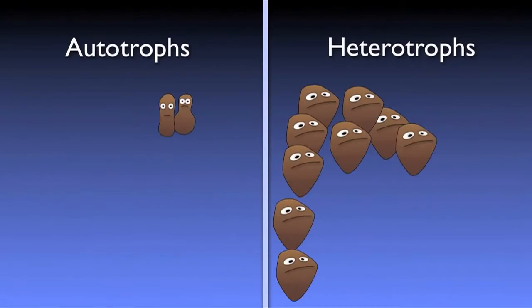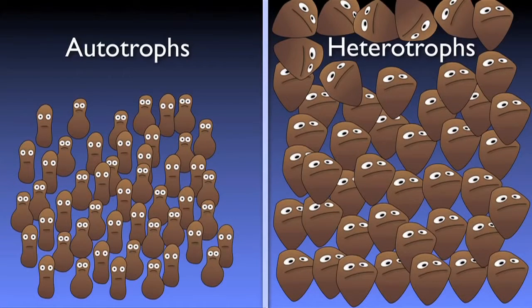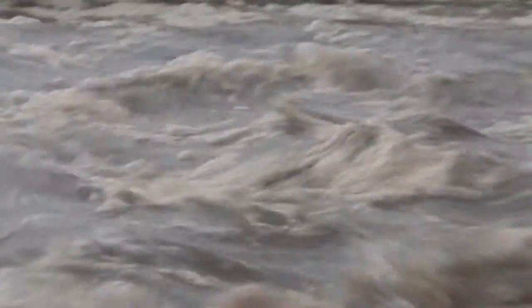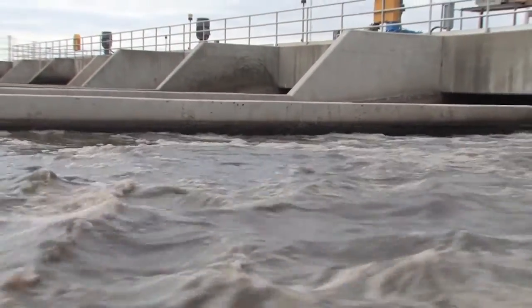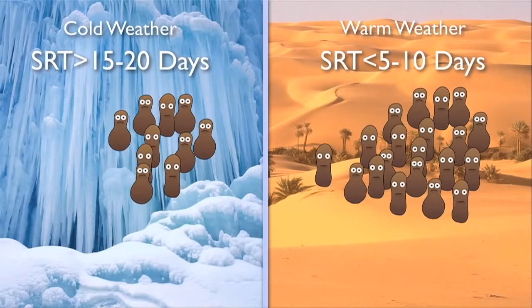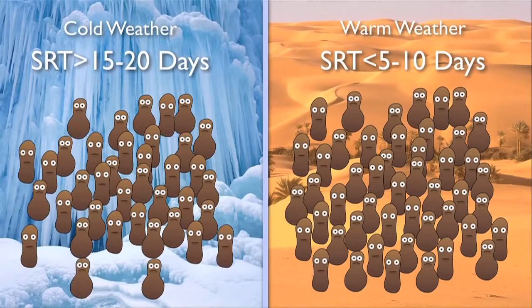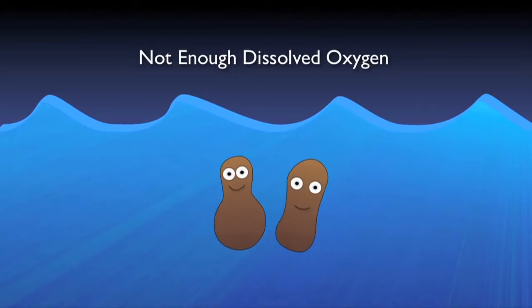In contrast to heterotrophic BOD-consuming bacteria, autotrophic nitrifiers require more time to mature and maintain their population in a biological wastewater treatment system. The nitrifiers dictate the SRT in nitrogen-reducing plants. How fast nitrifiers grow depends on the temperature of the wastewater and the amount of dissolved oxygen present. If nitrifiers aren't allowed enough time to thrive, you run the risk of accidentally wasting them out of the system entirely and losing nitrification. Higher temperatures and DO concentrations means faster growth. Colder temperatures and lower DO concentrations means slower growth. Also, when no DO is present, nitrifiers can become completely inactive.